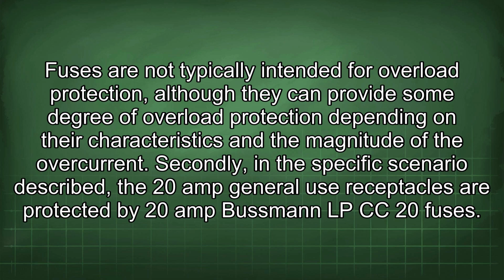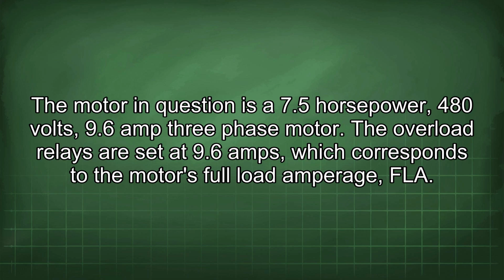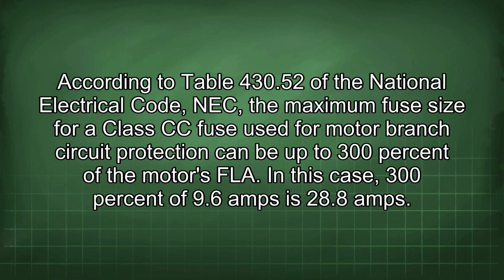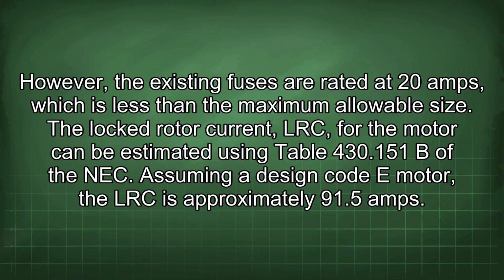Secondly, in the specific scenario described, the 20 amp general use receptacles are protected by 20 amp Bussmann LPCC20 fuses. The motor in question is a 7.5 horsepower, 480 volt, 9.6 amp 3-phase motor. The overload relays are set at 9.6 amps, which corresponds to the motor's full load amperage. According to Table 430.52 of the National Electrical Code, NEC, the maximum fuse size for a Class CC fuse used for motor branch circuit protection can be up to 300% of the motor's FLA. In this case, 300% of 9.6 amps is 28.8 amps. However, the existing fuses are rated at 20 amps, which is less than the maximum allowable size.